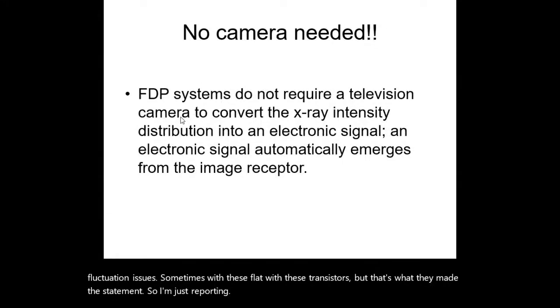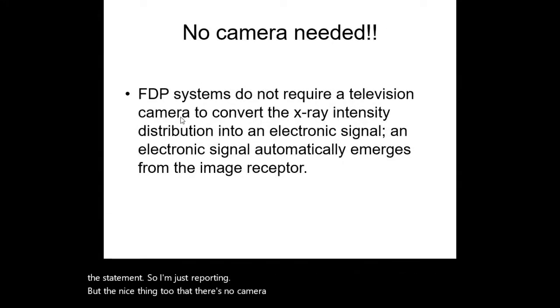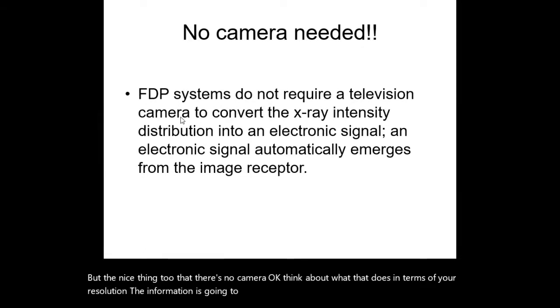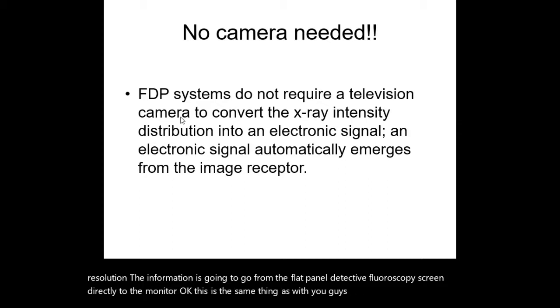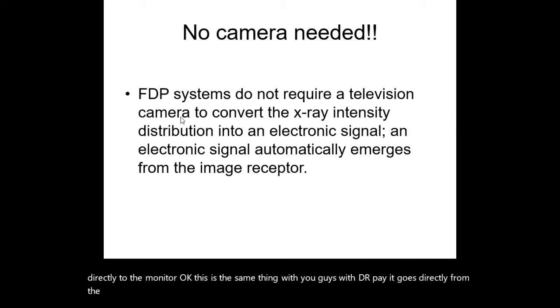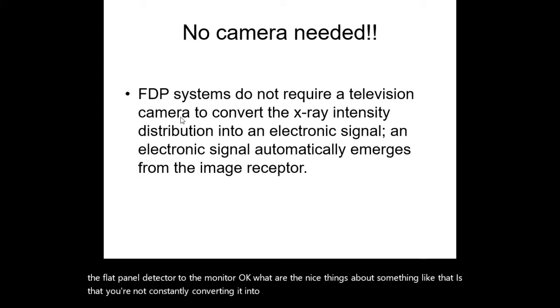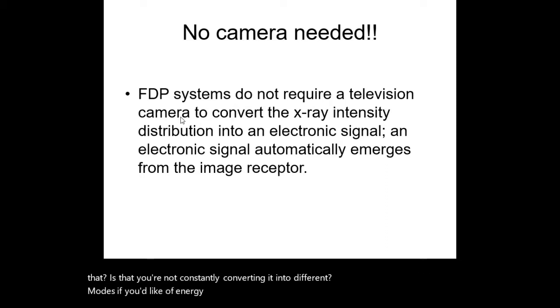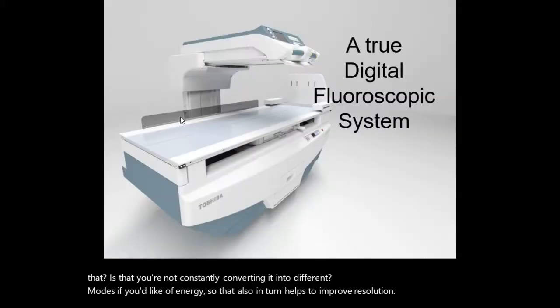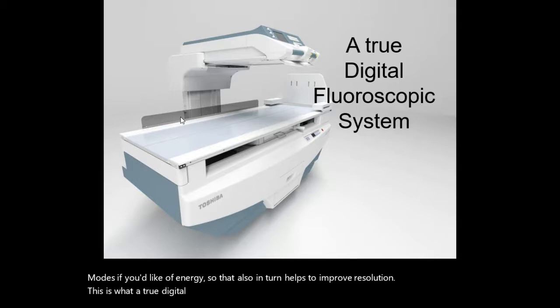But the nice thing too is that there's no camera. Think about what that does in terms of your resolution. The information is going to go from the flat panel detector fluoroscopy screen directly to the monitor. This is the same thing as with DR. It goes directly from the flat panel detector to the monitor. One of the nice things about something like that is that you're not constantly converting it into different modes, if you'd like, of energy. So that also in turn helps to improve resolution. So this is what a true digital fluoroscopic system would look like.